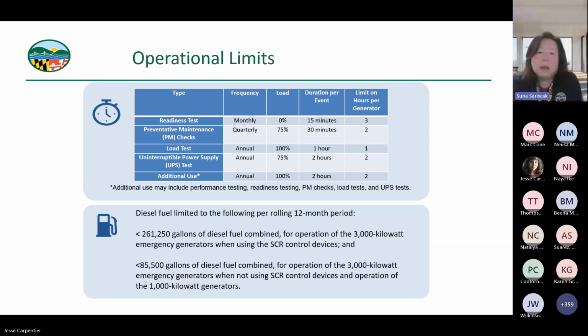And then for the diesel fuel limit, these numbers look unusual because they actually asked for 275,000 gallons and 90,000 gallons. But as Justin mentioned, fuel meters are not particularly accurate. We took 5% off of these numbers, and I know that makes the gallons much lower. The applicant had a lot of concern until they recognized that it's really only if their rolling 12-month total is approaching 25 tons. So they can go over those numbers. They just have to demonstrate to us, and they're going to be keeping a lot of records and submitting reports to that effect. Next slide.